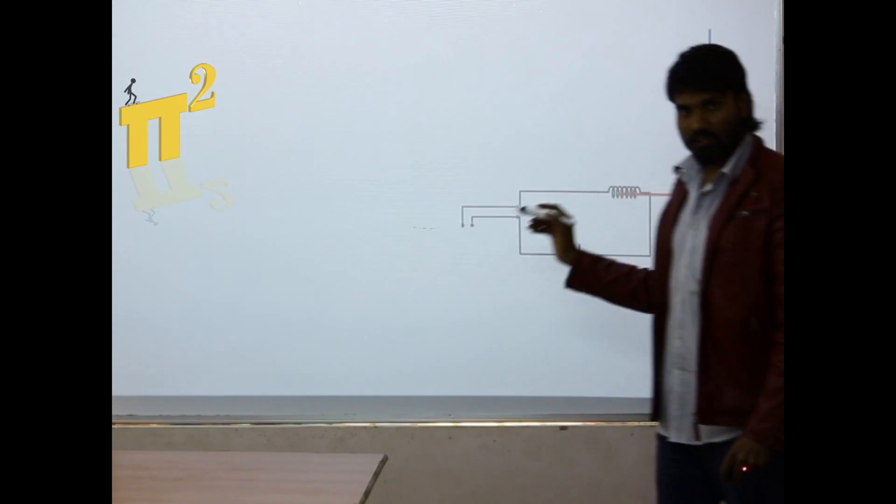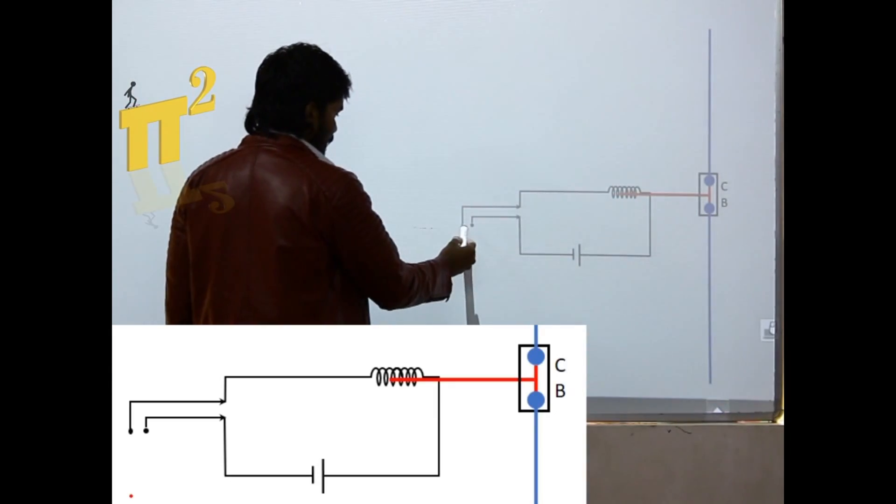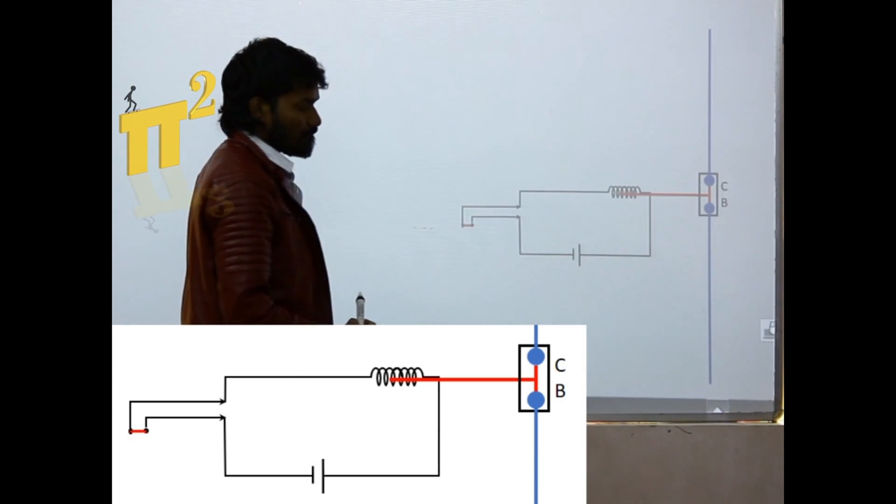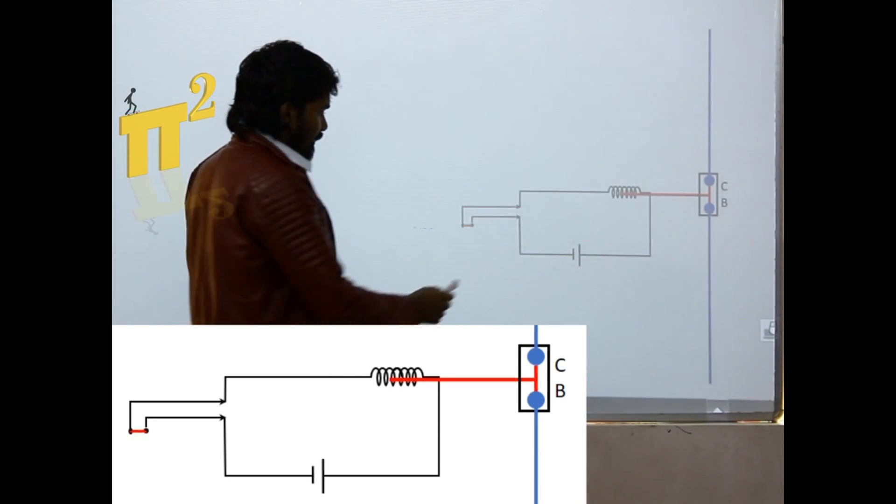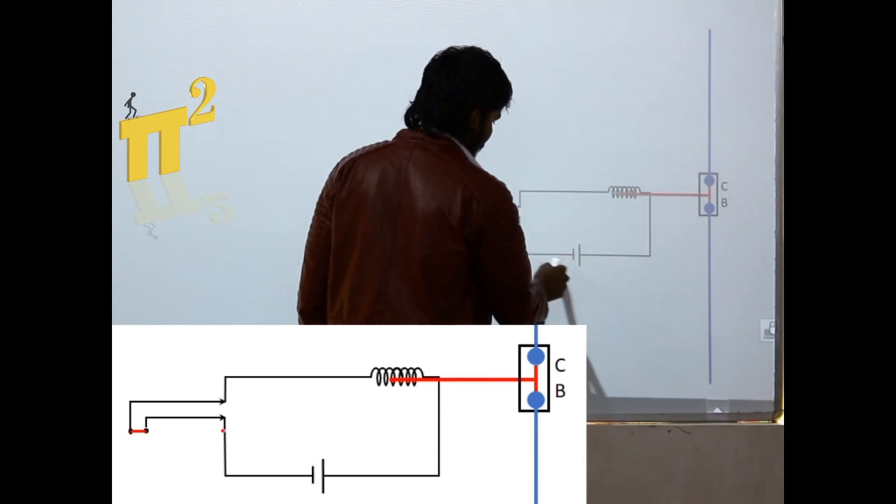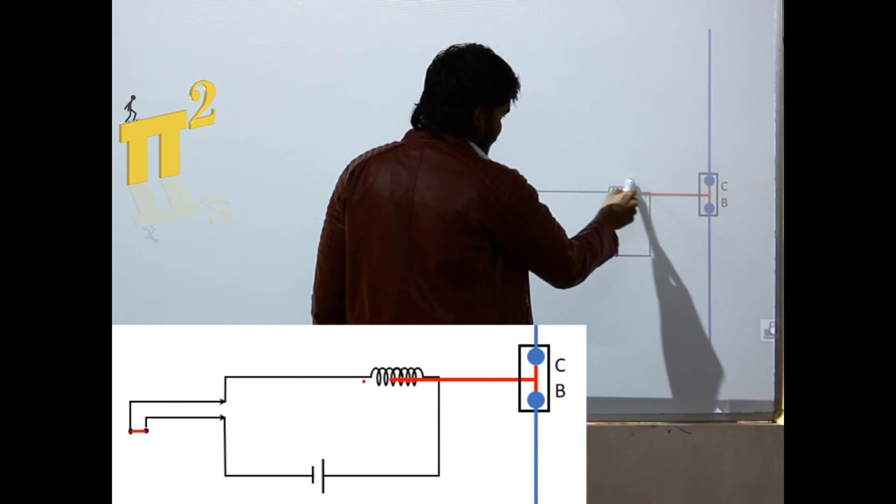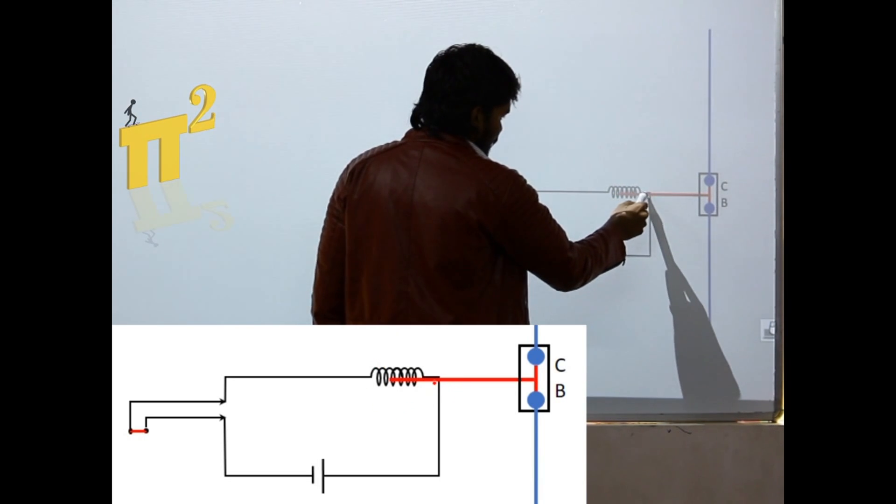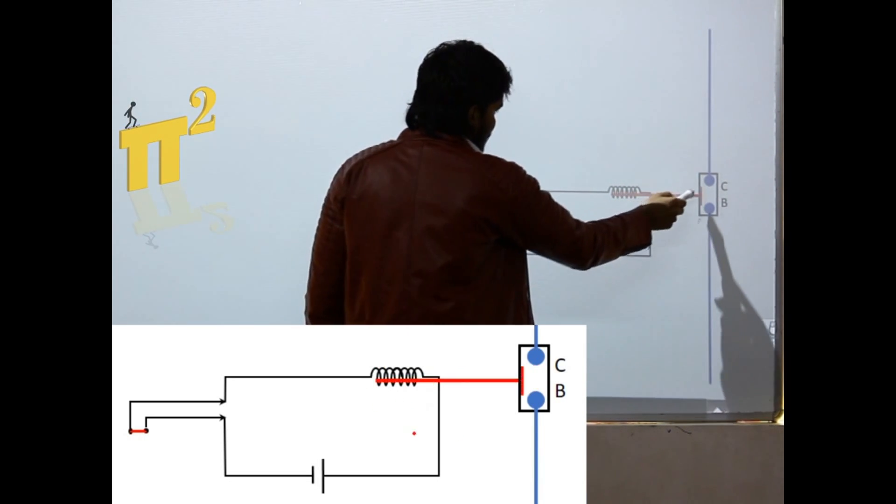When there is a fault, if I could short these two contacts, then current flows through this circuit. Hence this trip coil will attract this plunger inside and the circuit breaker is opened.